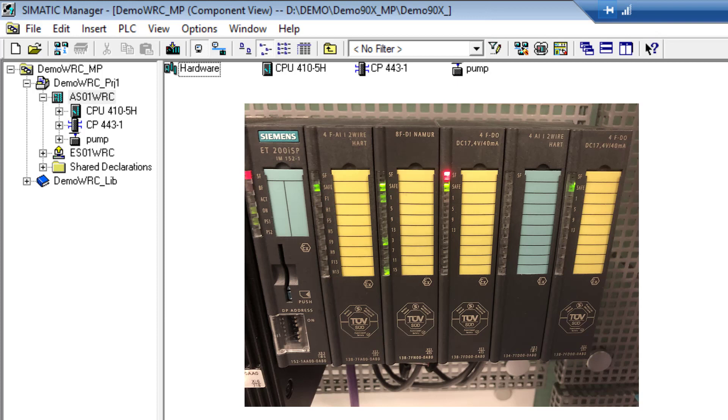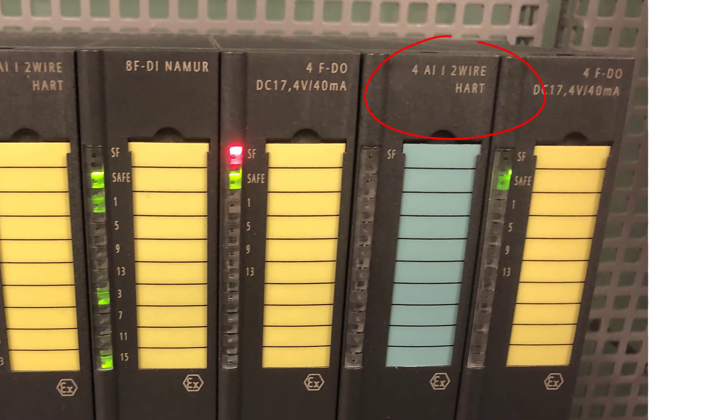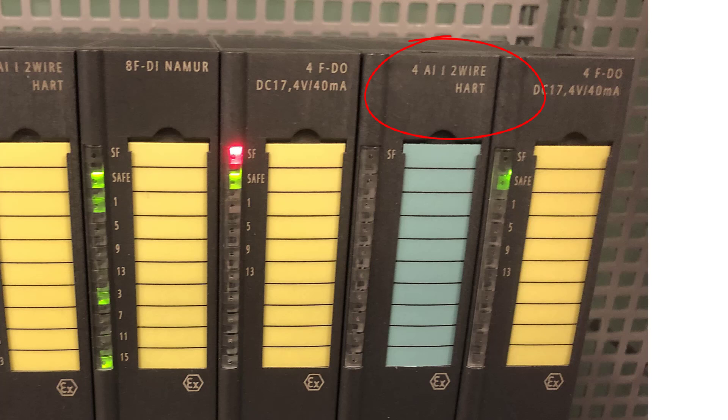The ET200 ISP is remote I/O for hazardous areas. It normally comes in a stainless steel enclosure that's pre-approved with your I/O cards in there, and the milliamp input cards are HART enabled or support HART pass-through as standard.